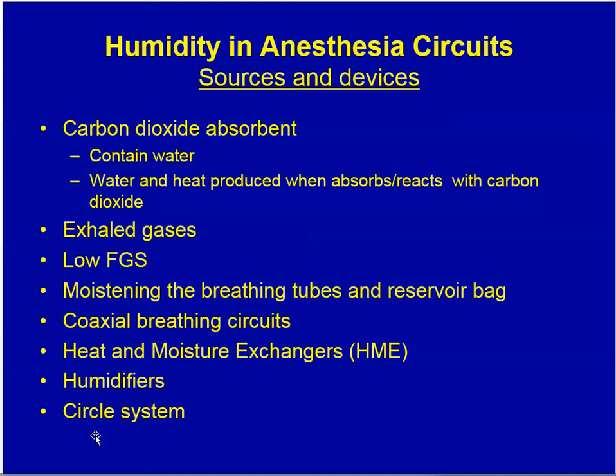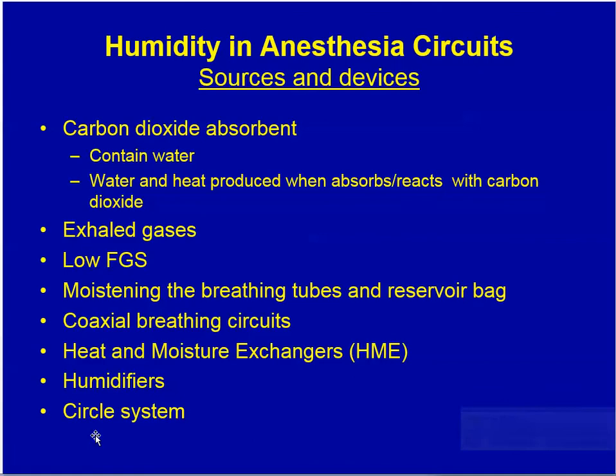How do we get humidity into anesthesia circuits? One source is the carbon dioxide absorbent, which contains water, and water and heat are produced as it reacts with carbon dioxide. Exhaled gases, of course, contain warm humidified gases. Humidity is favored by low fresh gas flow, by moisturizing the breathing tubes and reservoir bag, by use of coaxial tubing, heat and moisture exchangers, humidifiers, and the circle system.